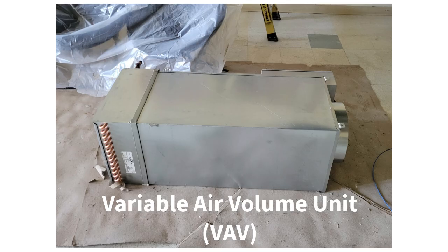However, it doesn't work so well in our 20-some odd office spaces, where some are on the north side, some are on the south side, east, west, different sun, different personal preferences. So the way we handle that is the air handling units and the geothermal system send air at a certain temperature, either heated or cooled as is appropriate, to a zone, and that would go to like 20 or so of our offices. Then there are about 20 variable air volume units, and that's what you see there on the floor. That takes the air coming down from the air handling unit, and it can heat it up or cool it down and adjust how much of it goes into each individual office. And so by doing that, that's how you can have all of your offices at different temperatures depending on time of day and preferences of the occupant in the room.